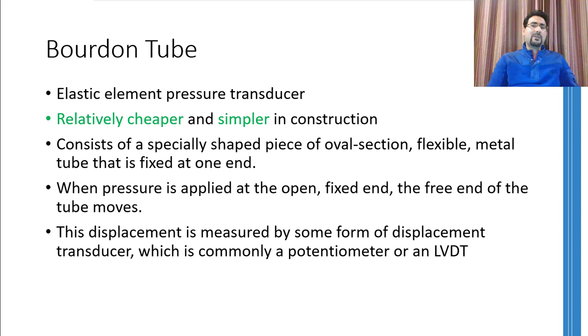Just like diaphragms, they have one open end from where the pressure is applied, whereas the other end is closed and normally free to move. The movement of this free end is measured to figure out the applied pressure. Once again, the task is to measure the displacement, so any displacement measuring sensor can be used over here as well. Primarily, there are three major types of Bourdon tubes.